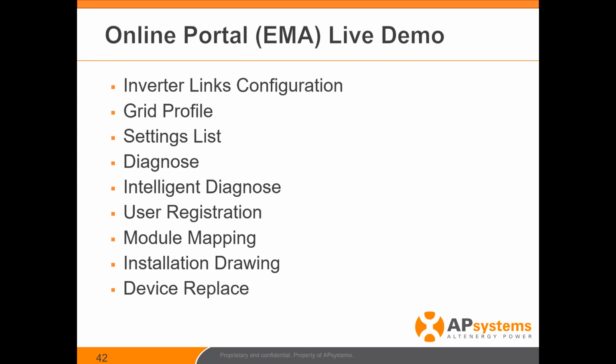We talked about this earlier with 600 and QS1s. Let's say you use that in a commercial environment. You're going to have to change the grid profile to meet the requirements for 208. Let's say you live in California. You're in Rule 21 country. You need to change the grid profile.